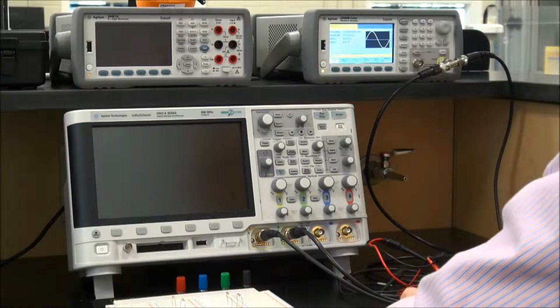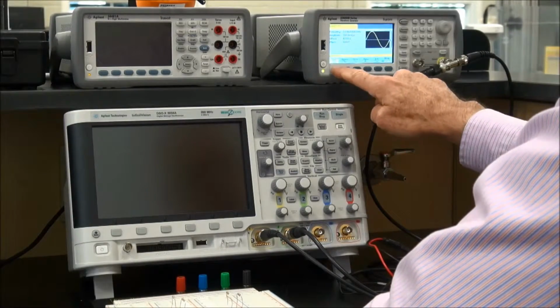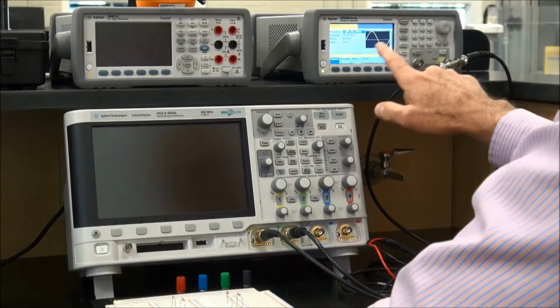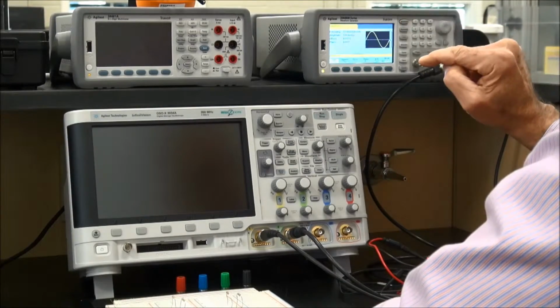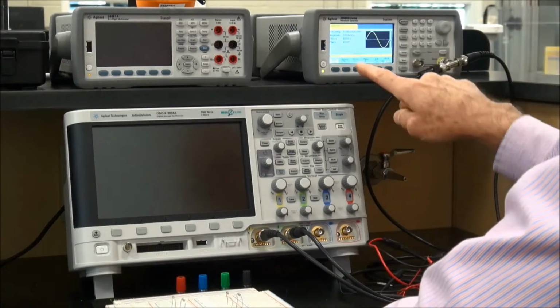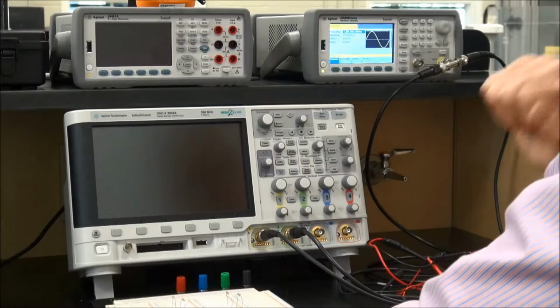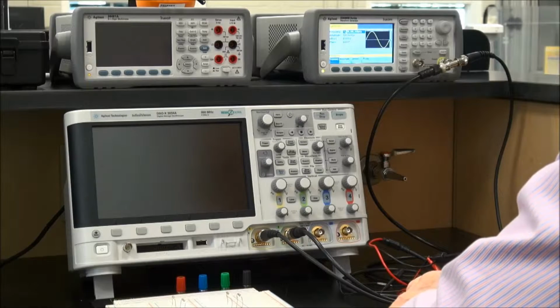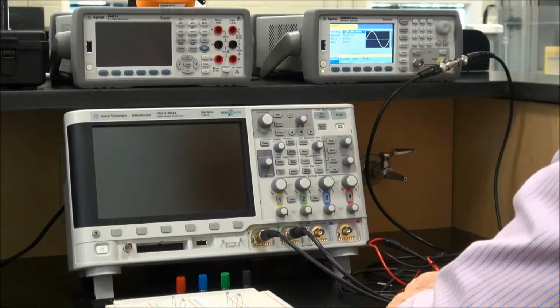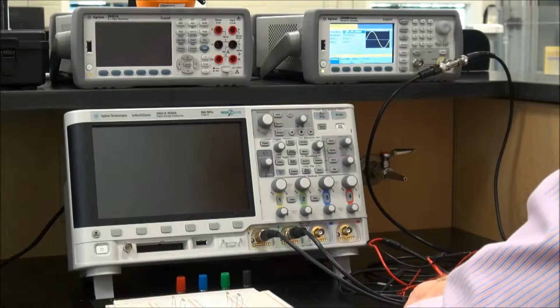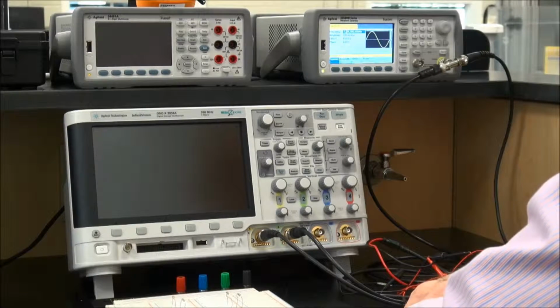What I'll do is, I've already selected sine wave, and when I push that, you see I get some parameters. Now I could have gone back, hit waveform, and since sine wave is highlighted, I could have pushed the key parameters, and I would see the 4 parameters that describe a sine wave appear in front of me. Now the frequency I'd like to change from 1 kilohertz to 100 hertz.